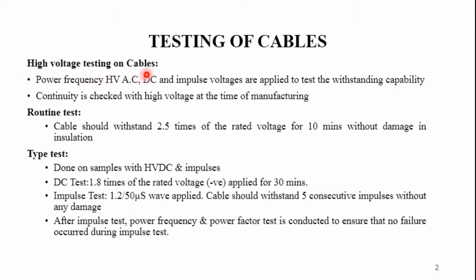High voltage testing on the cables. The cables are tested for withstand voltage using power frequency HVAC, DC and impulse voltages. At the time of manufacture, the entire cable is passed through a high voltage test at the rated voltage to check the continuity of the cable. As a routine test, the cable should withstand 2.5 times the rated voltage for at least 10 minutes without any damage. Then we can call it a routine test.